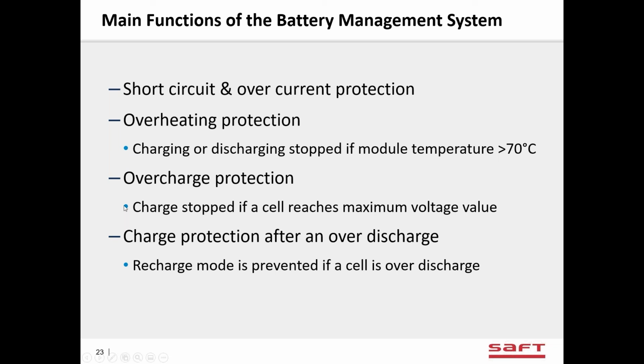And another one that's interesting with lithium-ion is if the battery is over discharged. When I say over discharged, I'm talking about less than 2 volts per cell for most of the batteries. LTO, you can go a little bit lower than 2 volts per cell, but below 1 volt per cell for sure, the battery starts to dissolve the copper that's on the anode, and the copper can become a short circuit. So if it's been at a low voltage for an extended amount of time, you have to prevent the discharge or prevent recharging.